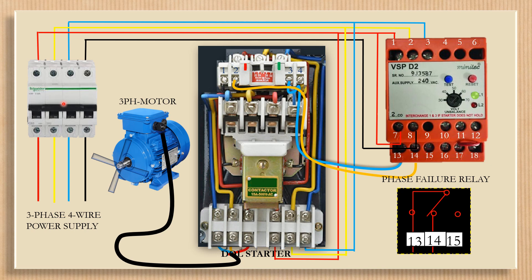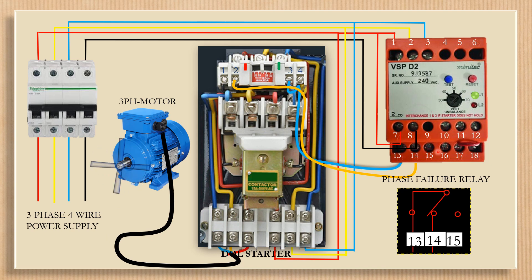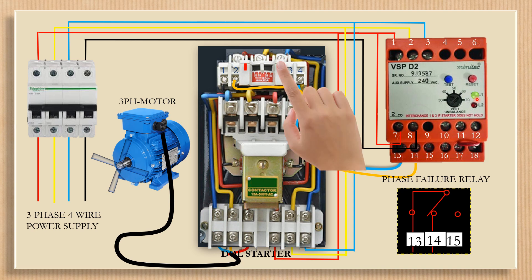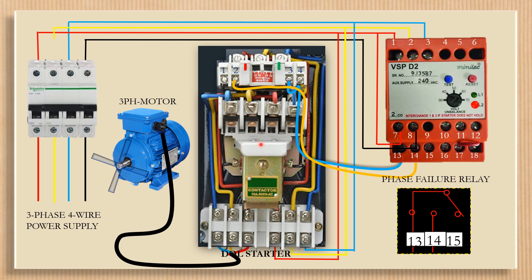Now start the motor by pressing the start button. Test the delay by pressing the left side push button. Reset by pressing the reset push button. Now suppose a phase wire is disconnected due to burning of a wire, etc. The SPP single phasing preventer contacts 13 and 14 will be disconnected, and the contactor of the DOL starter will disconnect the motor circuit and the motor will stop running.